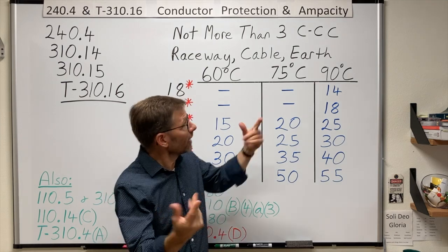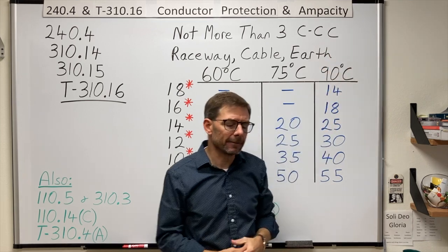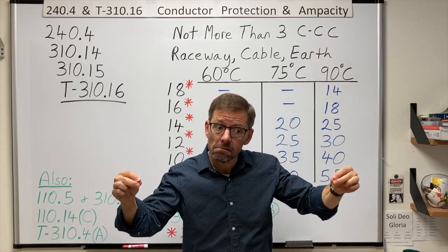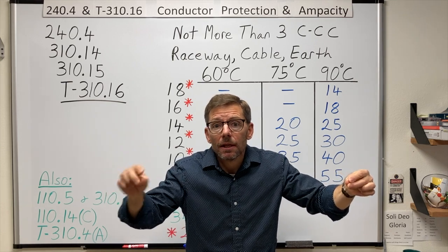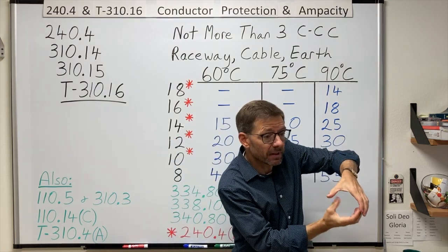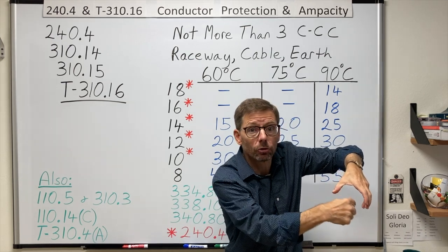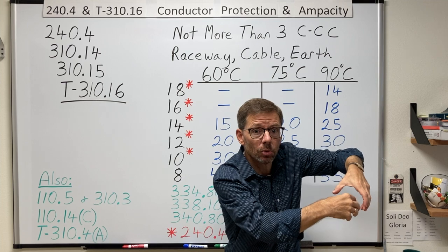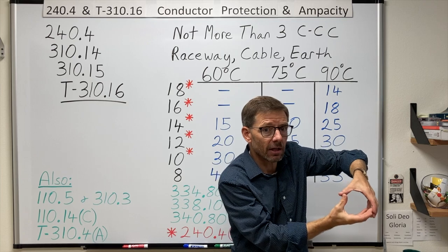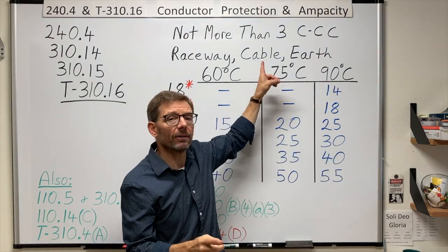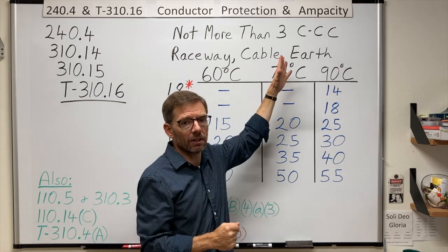Another adjustment, well, another question that comes up here, what is a current carrying conductor? Well, let's think about it. The ground, would I count that? No, it doesn't carry current, not in normal circumstances. Now, let's not get confused when we're talking conduit fill. How big of a conduit do I need for all the conductors I'm using? I count the ground there because it takes up space. That has to do with pulling in or pulling out conductors, not doing damage. So I count it there. But here we're more concerned about heat. What's generating heat? And the ground does not generate heat. So we do not count it here.